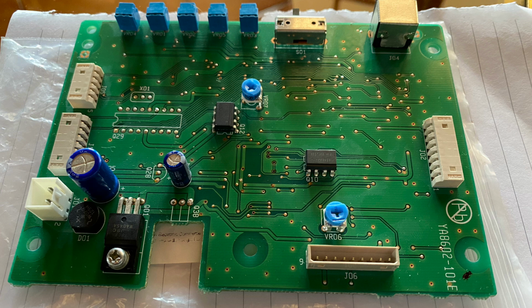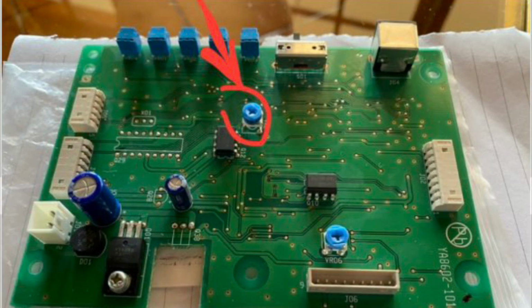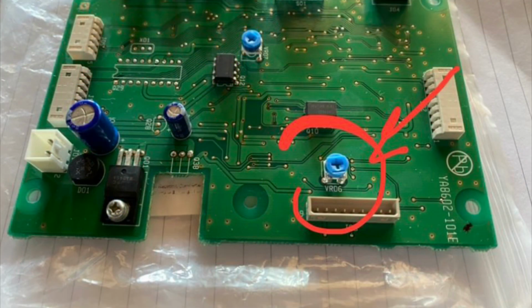Here you can see a picture of the board and you can clearly see two trim pots. One is this one here, and it's used to adjust the maximum voltage that you send from the controller to the rotor unit outside, which is supposed to be 24 volts, as the DC motor outside is 24 volts. So in my case, it was misaligned. It was not adjusted yet. And in fact, it was sending more than 24, about 26 point something. And I have dropped the voltage down to about 24.5, taking into account a little voltage drop along the cables.